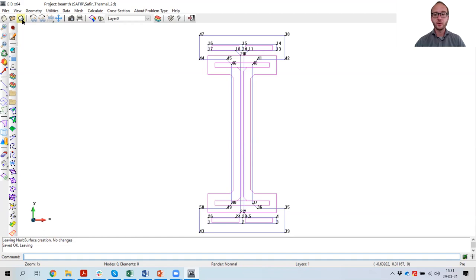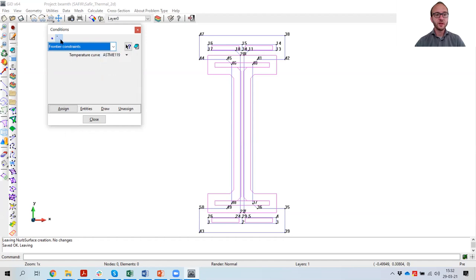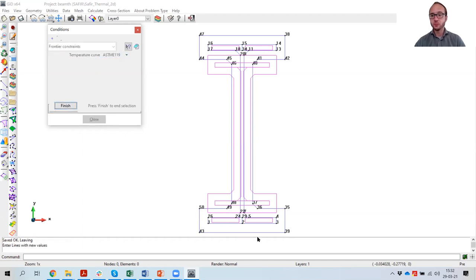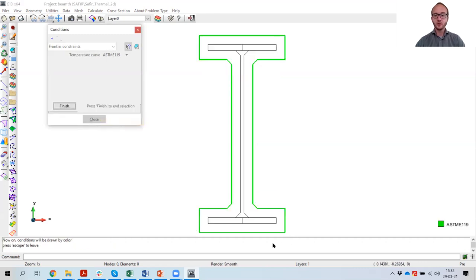This concludes the creation of the geometry for this beam. Now I go into the data menu and go one by one through the submenus. Starting with conditions: our beam is subject to the ASTM E119 fire on four sides, so I select the line frontier constraints and select the ASTM E119 temperature curve. I assign these to the exterior lines — in other words to the insulation material — going all around the profile. I can check by drawing the frontier conditions that I went all around and did not forget any boundaries.